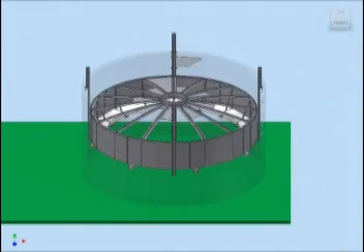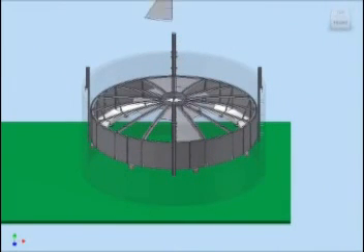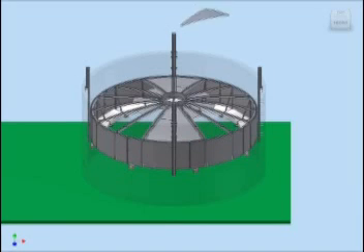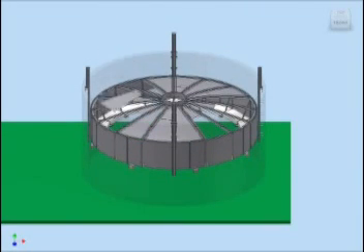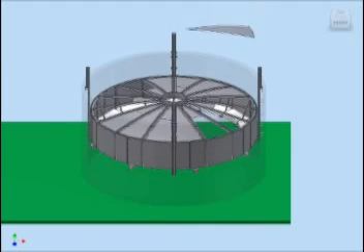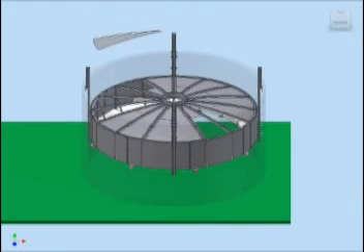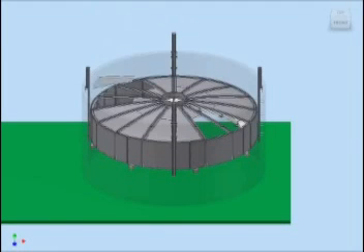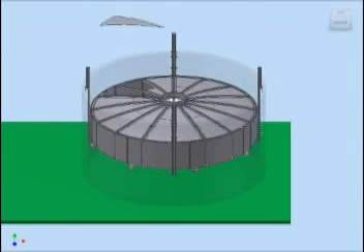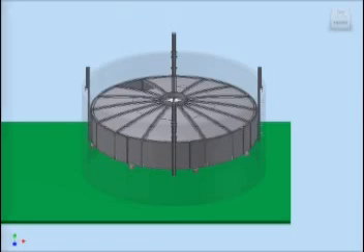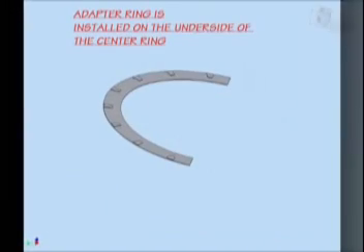Plate installation should progress from the outer perimeter to the center ring in a fashion that will balance the framework during the welding procedure. The inner portion of the cover plates are not required to butt flush with the center ring. The adapter ring is designed to cover any gaps that exist between the innermost cover plate and the center ring.